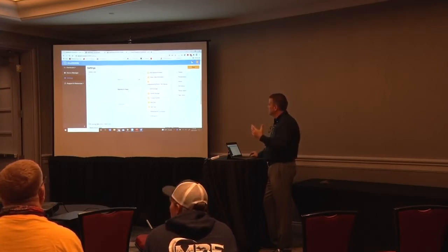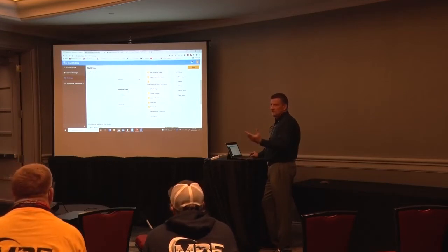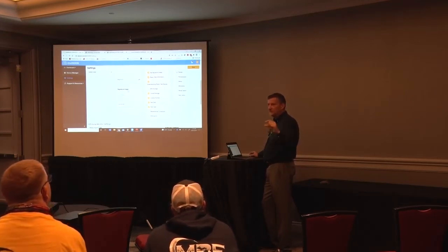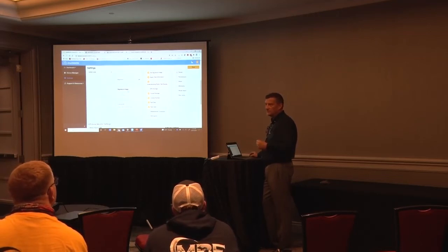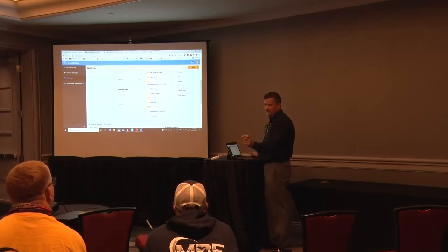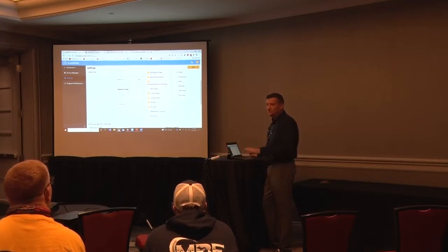I also want to mention that we now have measurement and survey. You can report that as an additional item in the summary data table. I can show this in a second in the report. And if you have a VOC CO2 monitor included, all of our additional modules already support that, it just needs to be enabled. You could chart that as well. It's up to you. There are no pass-fail criteria. It's just for reporting purposes, the monitoring.